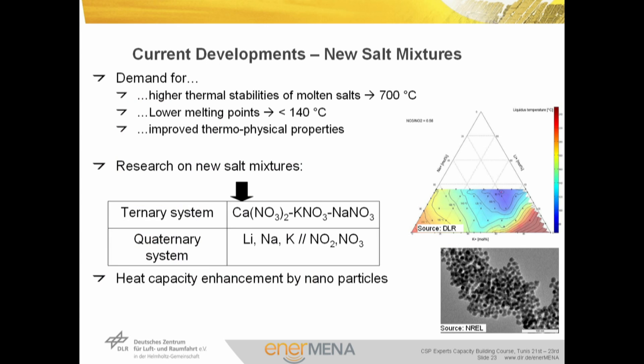Current developments in two-tank molten salt storage focus on identifying new salt mixtures that are cost-effective, operable at temperatures of at least 700°C, and show a melting point below 140°C. Research focuses on ternary systems with three components and systems with even more components. Another approach is enhancement of heat capacity by addition of nanoparticles.